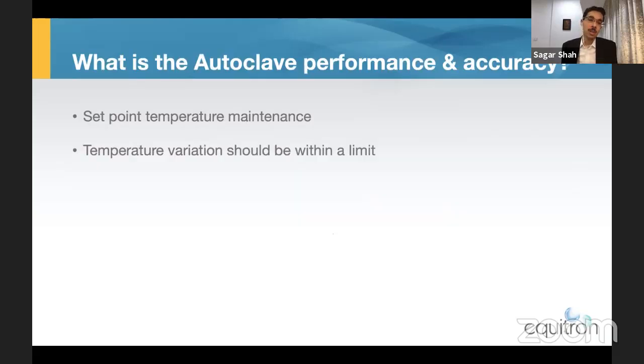What is the autoclave performance and accuracy that you're using? A good autoclave is able to constantly maintain the sterilization temperature in the band of about 1 degree Celsius once it reaches 121 degrees Celsius or 134 degrees Celsius. So for example, if your autoclave reaches 121 degrees Celsius, which is your sterilization set point, the autoclave temperature variation should not exceed much above, let's say, 122 if it was a 121 degrees Celsius set point, and 135 if it is a 134 degrees Celsius set point. So it has to be in that band of approximately 1 degree Celsius.